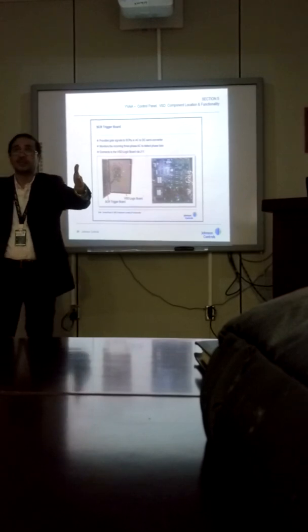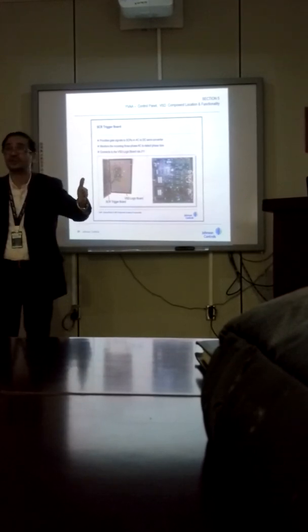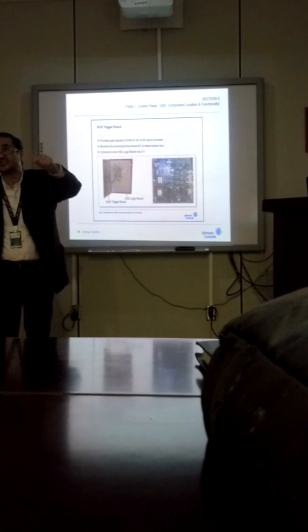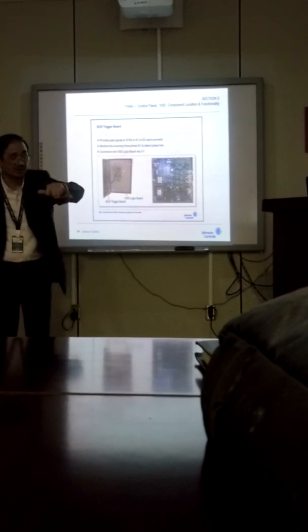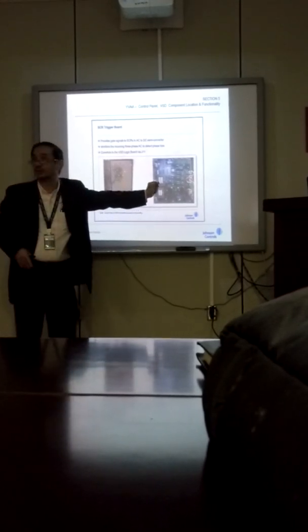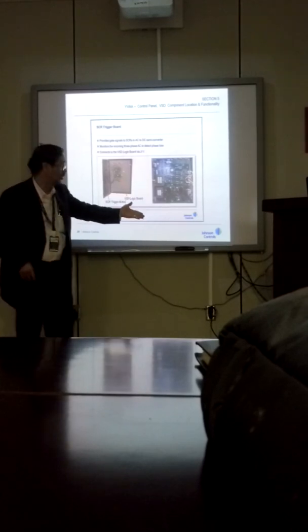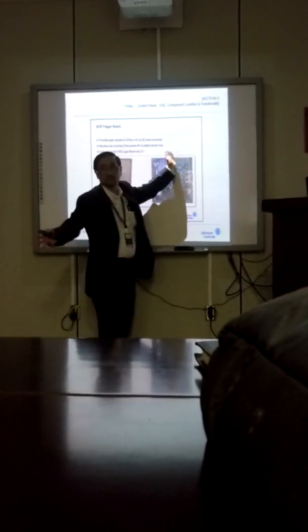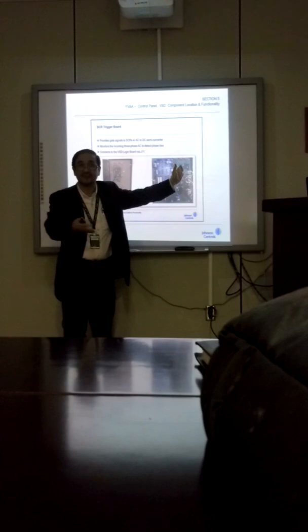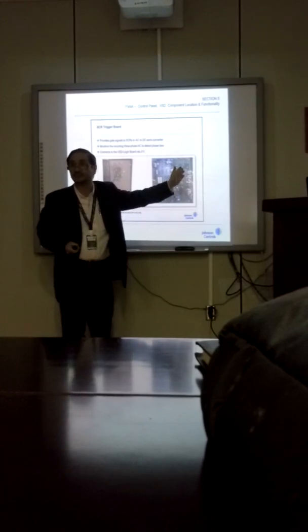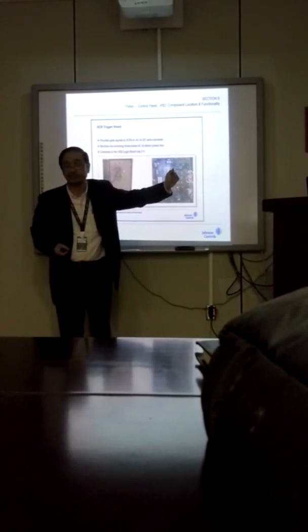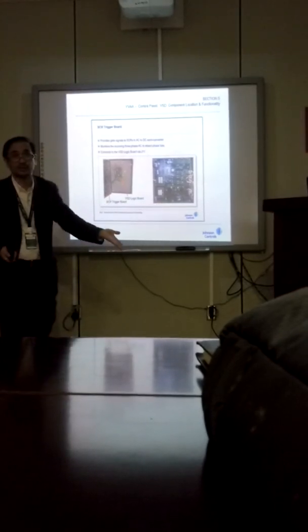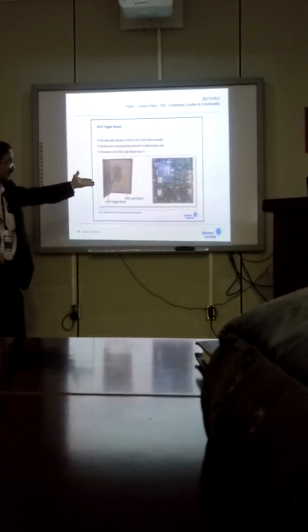Because remember, what is 60 cycle per second? 60 hertz. Even one of that 60 hertz, if it's lost, this monitors that. So the machine will not run because you have one phase out. You don't want single phase in the motor, right? Yes. What happened? It will burn the motor. It's a compressor also, it will burn our compressor. So it's a safety feature here.